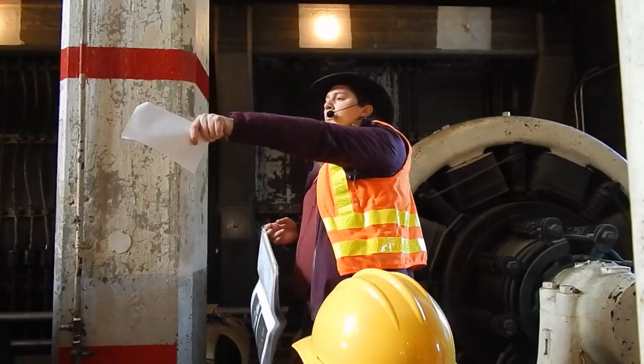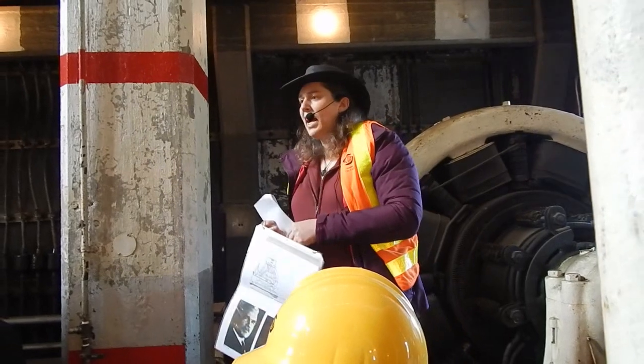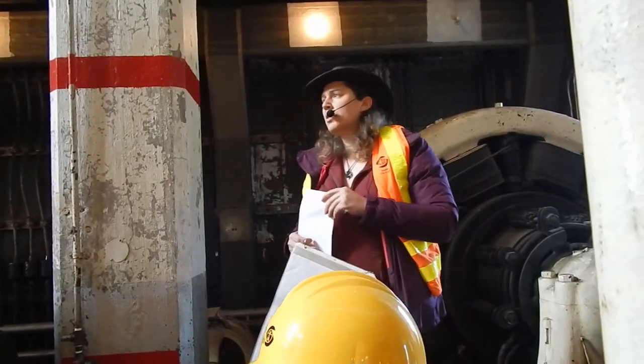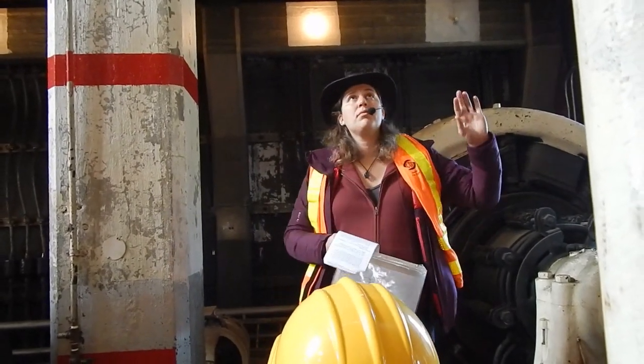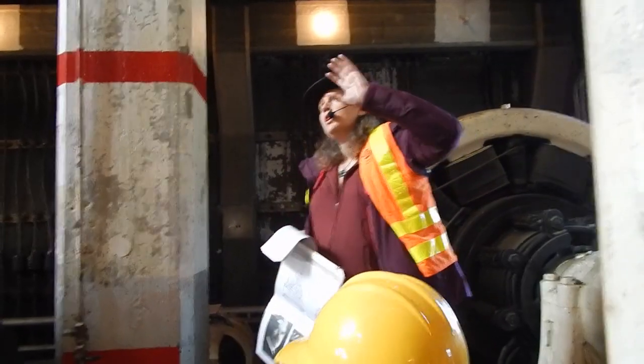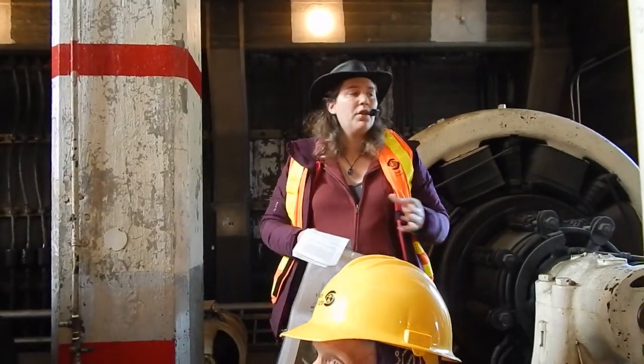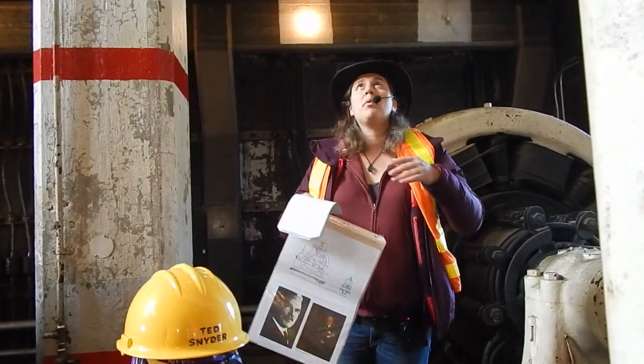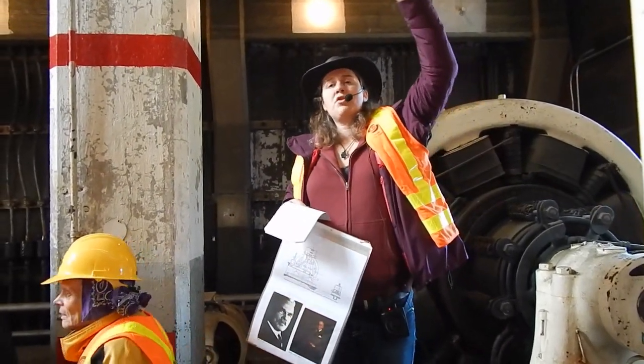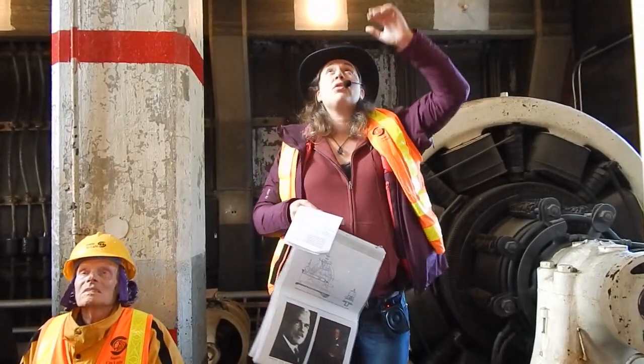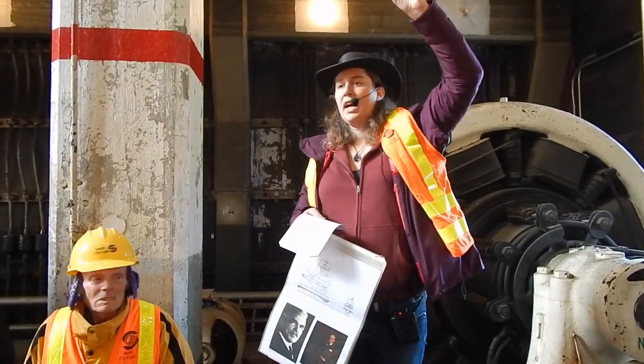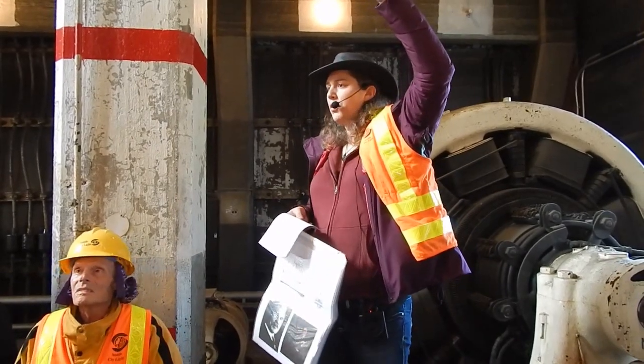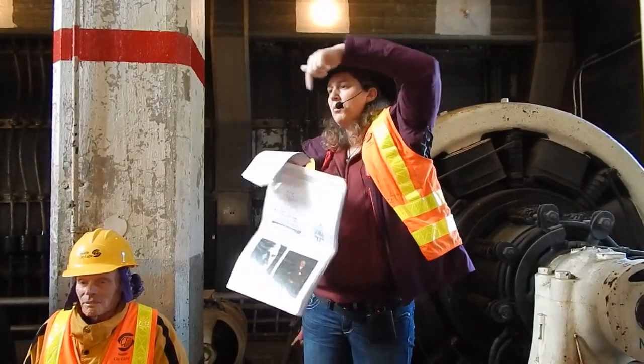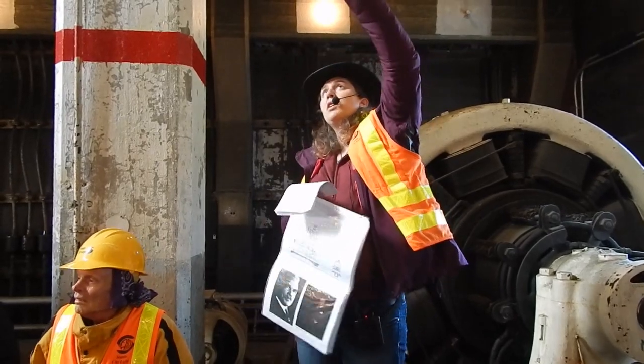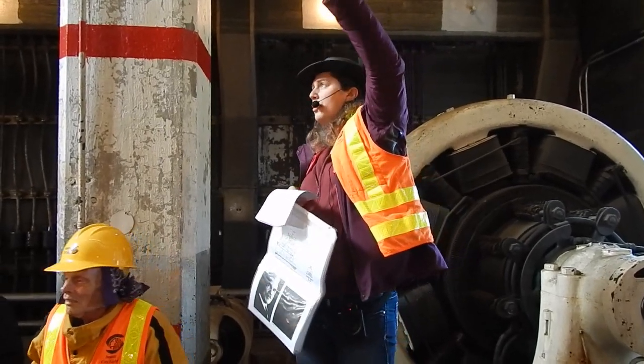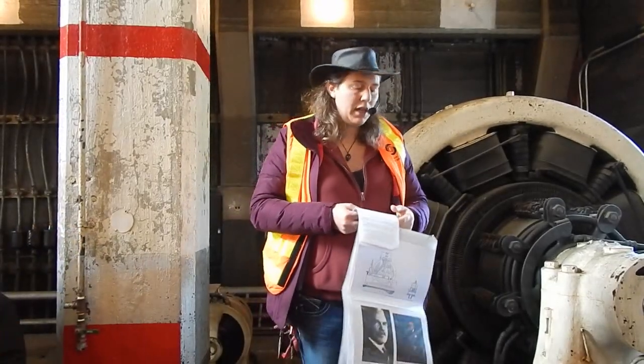One other thing, these pumps over here are actually step-bearing oil pumps. I'll touch on this again later, but these vertical units were really cool. They save a lot of space with the vertical design, but one problem was that putting the generator on top of the steam turbine puts a lot of weight onto it, so they had to have a huge step bearing in the middle, a huge bearing to keep both rotating masses from colliding with each other, with a lot of oil and pressure to keep these machinery pieces apart.